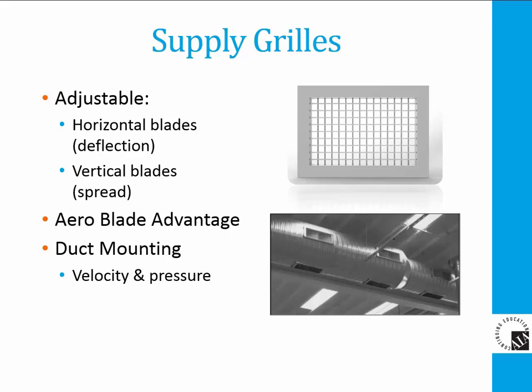An enhanced performance feature of supply grills is an airfoil shaped blade, which will reduce noise and pressure. For design, it is recommended that air velocity in the supply duct be less than 1,000 feet per minute. Also, static resistance at the outlet must be at least 1.4 times the velocity pressure of the supply air to avoid turning the air from an outlet to an air inlet.